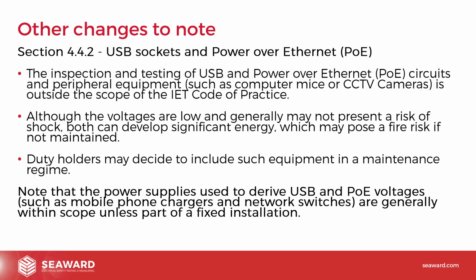Also something to note, power supplies used to derive USB and power over Ethernet voltages, such as mobile phone chargers and network switches, are generally within the scope unless they're part of the fixed installation. So although the actual equipment themselves, like a USB mouse, wouldn't be within the scope, the actual charger or the computer that provided that energy, which actually supplied that equipment, could well be within the scope of the Code of Practice. So again, it's important that even things like USB sockets and power over Ethernet equipment are checked and risk assessed by the duty holder to see how they want to deal with these things.